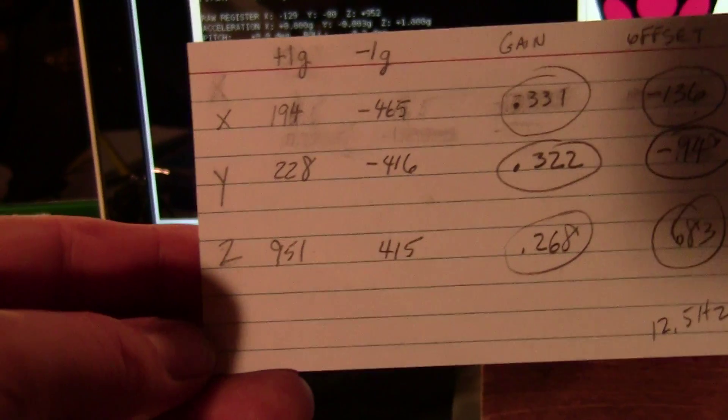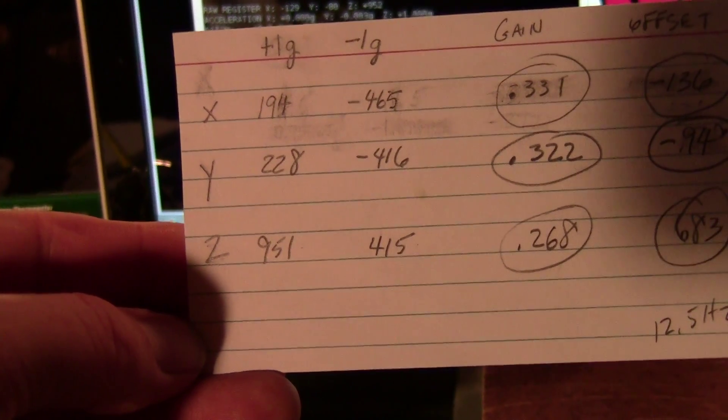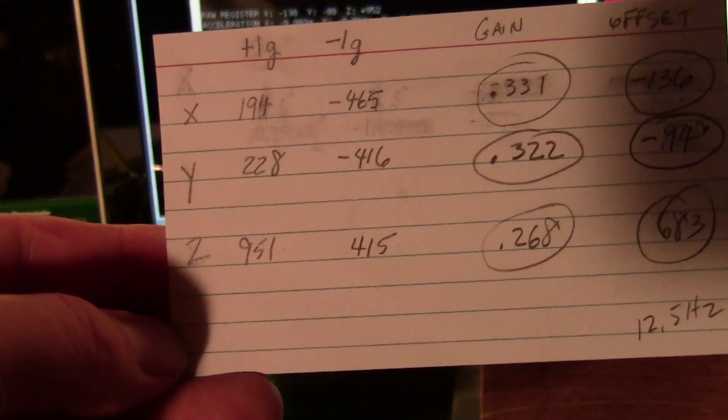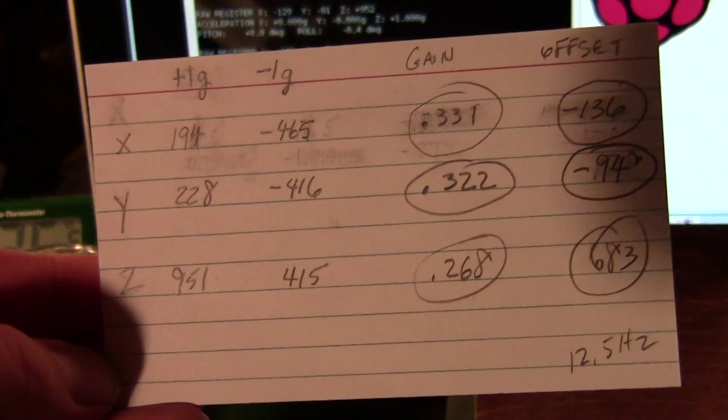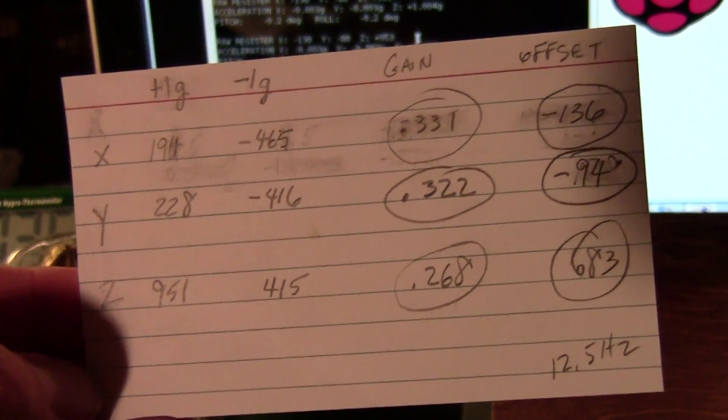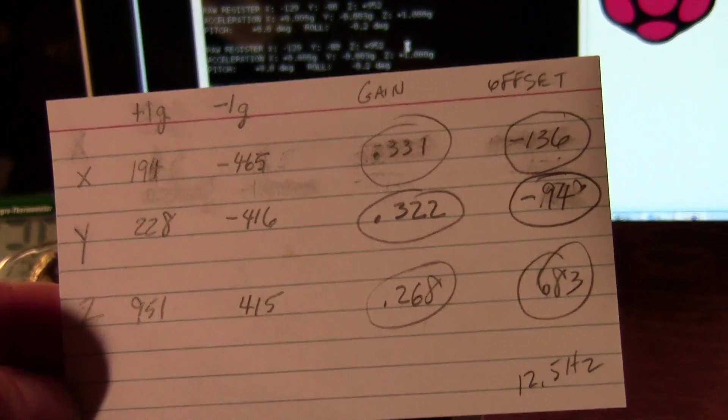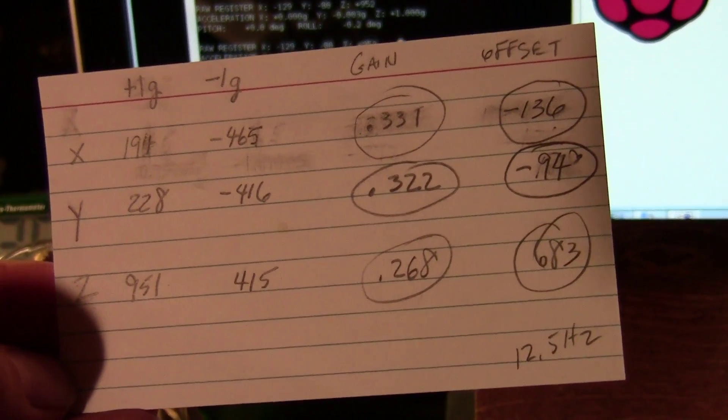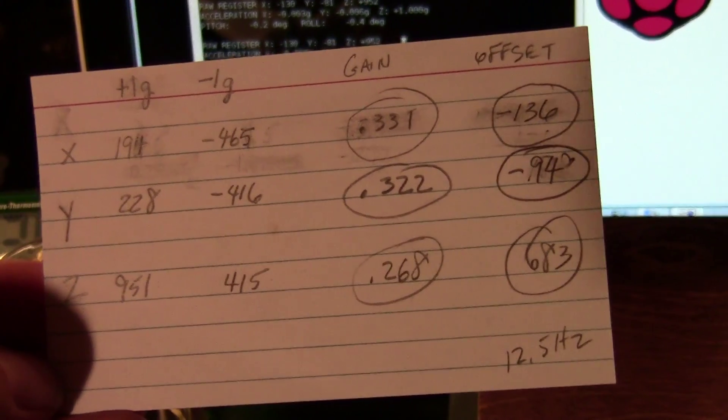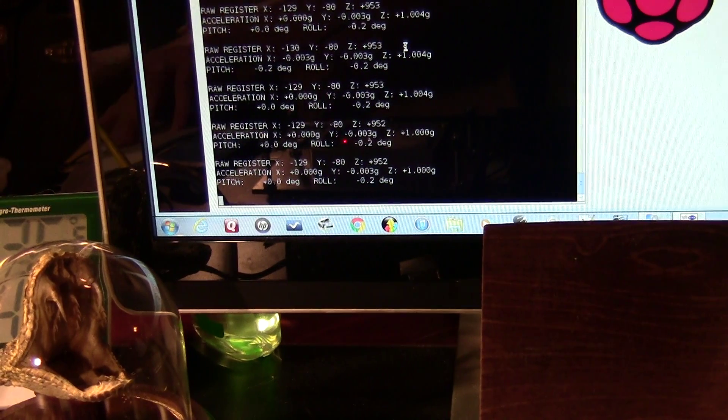In each of the three axes I recorded the value of the register. Then you use those equations to calculate an offset and a gain factor for each one, and those are the values that you put into the equations in the software.